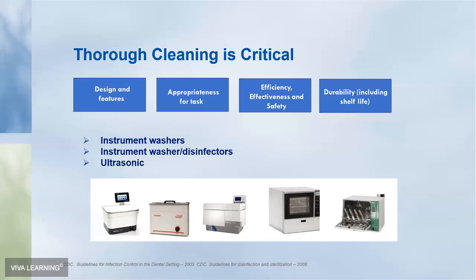In the case of ultrasonic cleaners, you would first of all place them in a rack or a designated container, and then place them in the ultrasonic cleaning solution. It's important that you don't place them on the base of the chamber or at the side, against the sides of the chamber. The way the ultrasonic cleaner works, obviously, is it cavitates, it produces bubbles. Those implode, release energy, and that cleans or mechanically cleans debris from the instruments that are in the solution. So if you have them against the base or against the sides, you can't get proper cavitation because there isn't space there between the instrument and the ultrasonic chamber itself. So you won't get implosion in that area, therefore it won't be clean in that area.